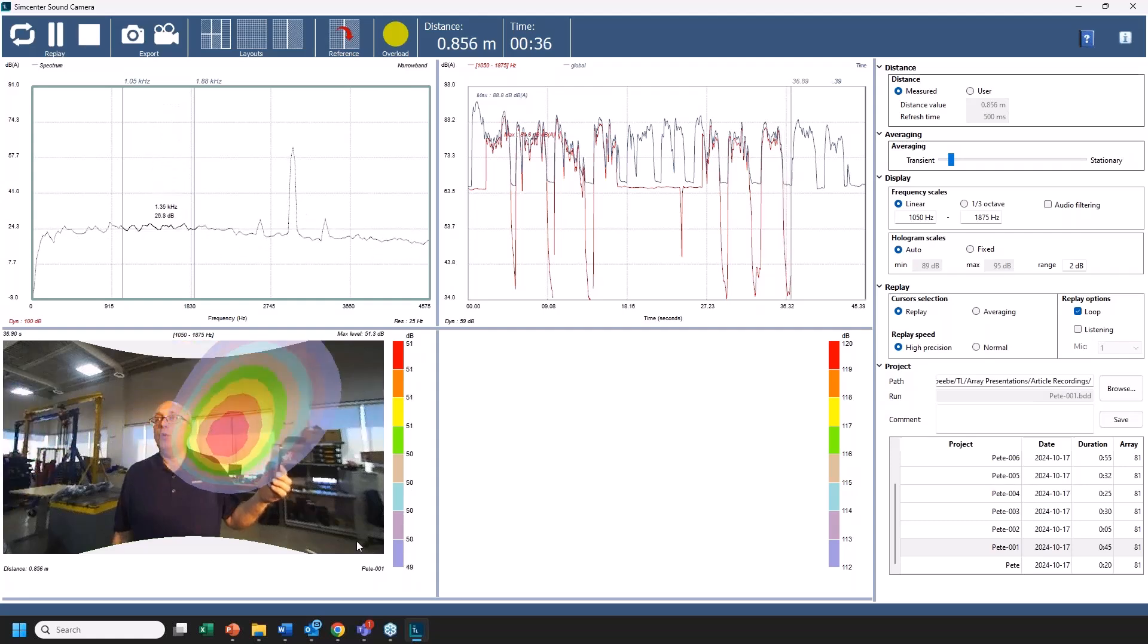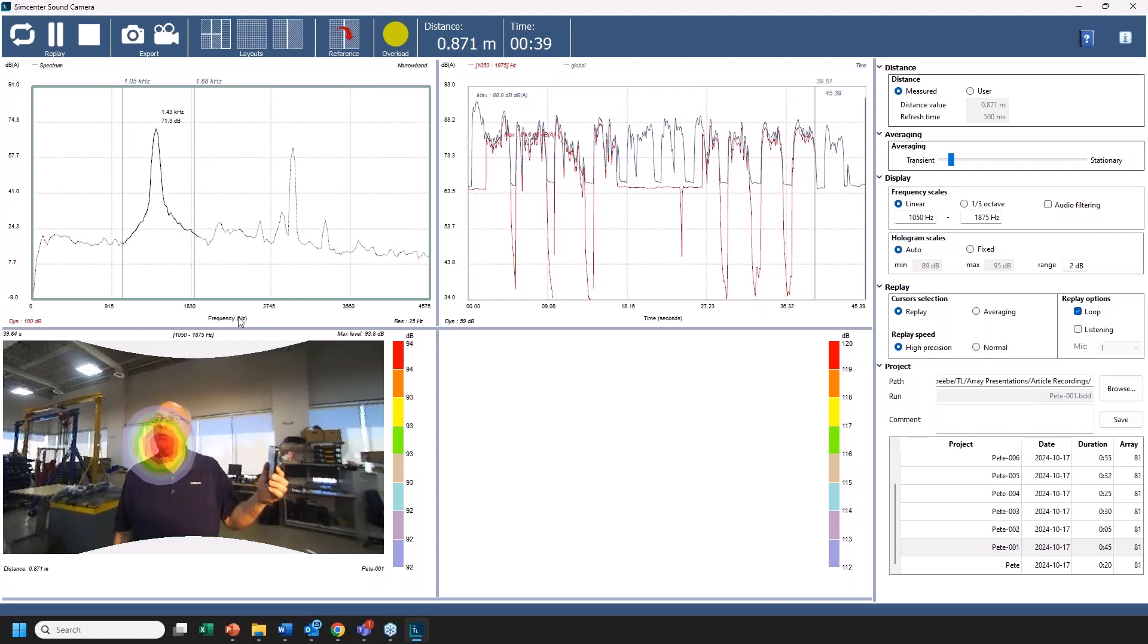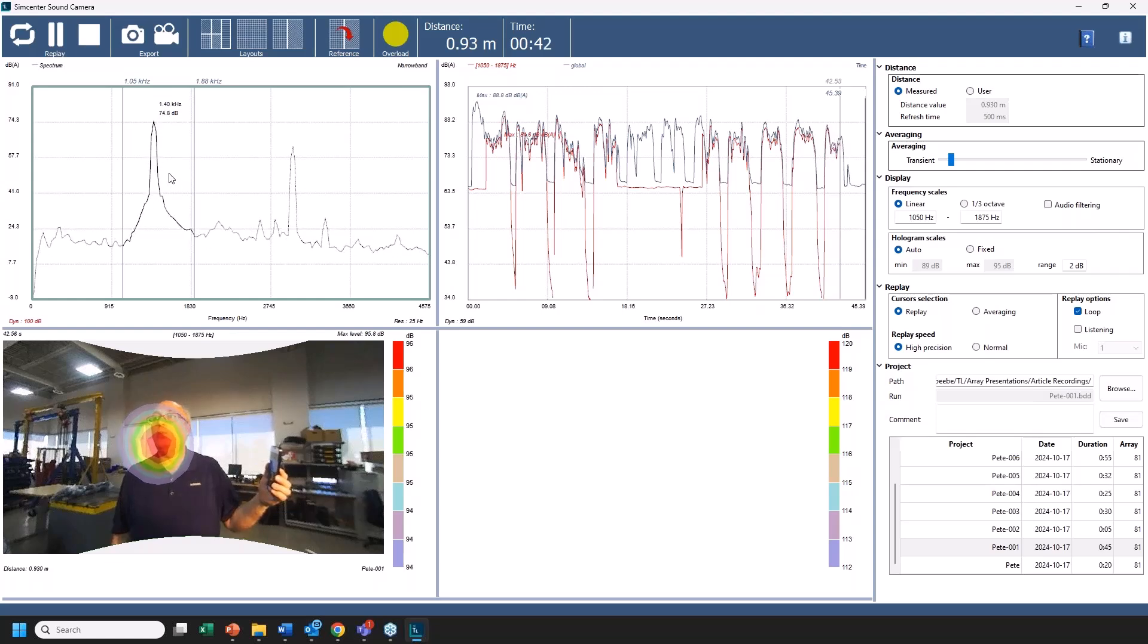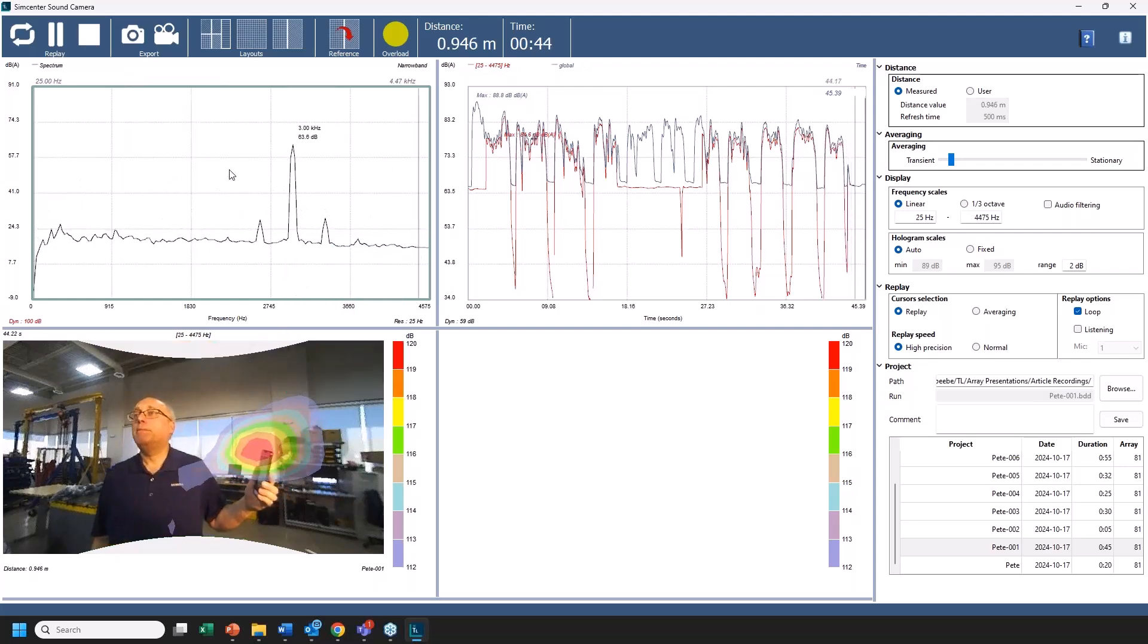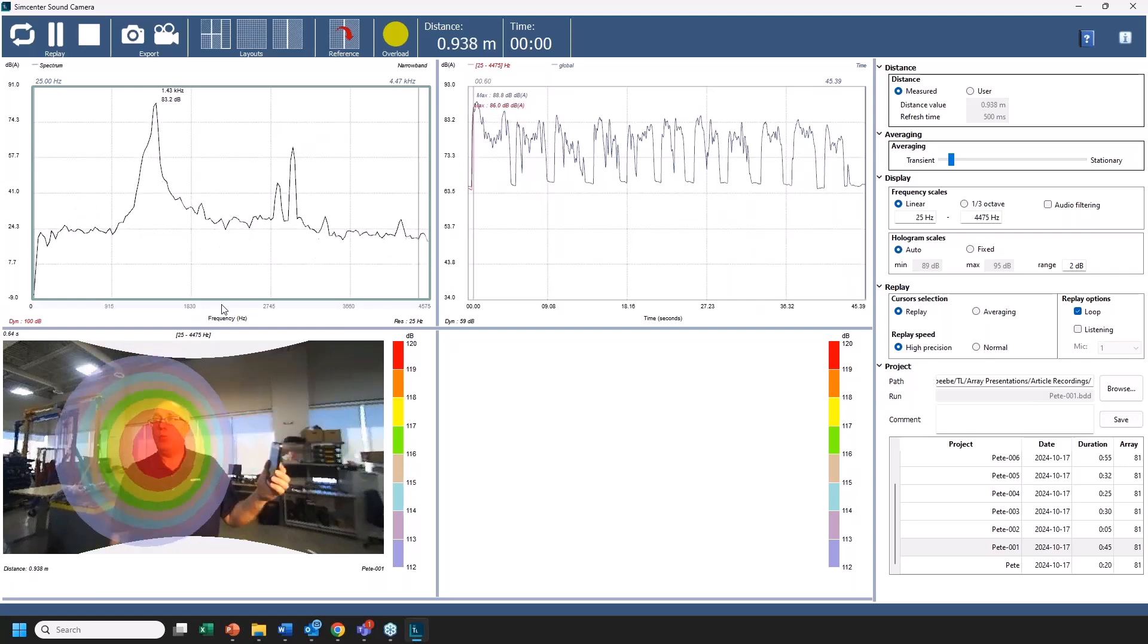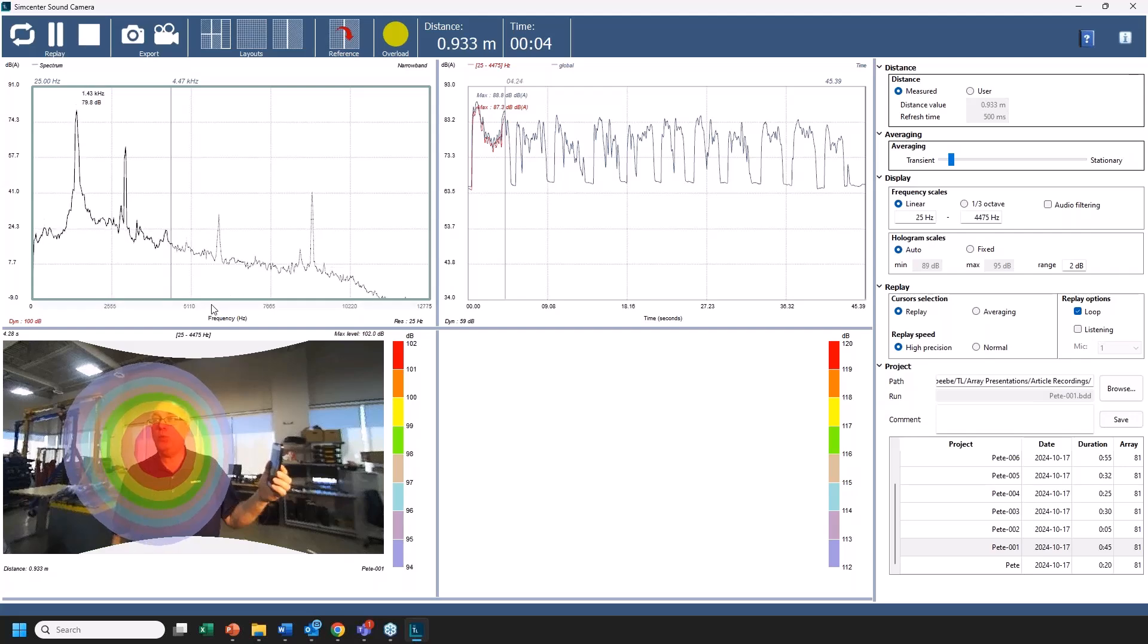I noticed frequency graph, live graph goes up to 4,475 hertz. Can you zoom in, zoom out there? You absolutely can. So the easiest way to zoom in is to look at where you have your double cursor. If you place your mouse arrow within that double cursor and scroll up with the scroll wheel on your mouse, you can zoom in to that tighter range. And if I zoom out from that, I can also just hover on the x scale here. If I scroll up that zooms in tighter, and if I scroll down I could go and make that range as far as my bandwidth, which in this case is 12.8 kilohertz. Oh, neat.